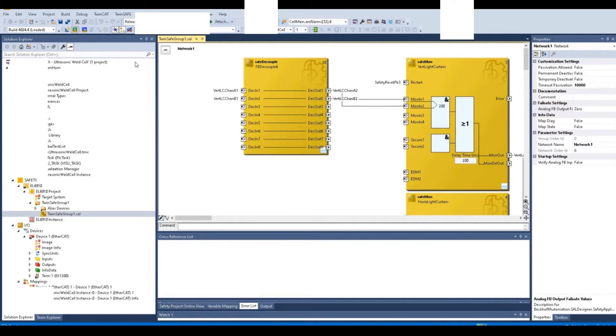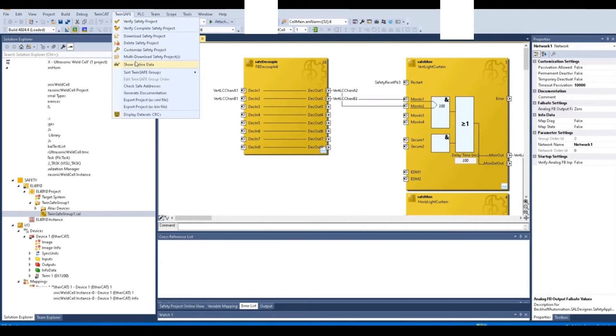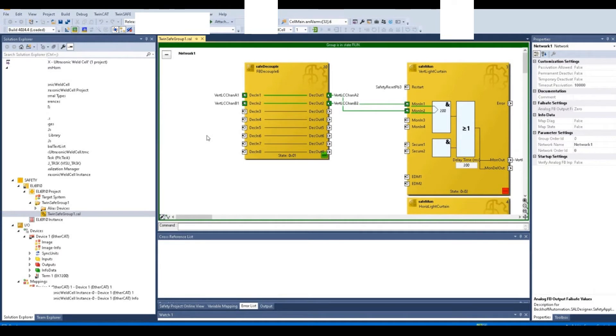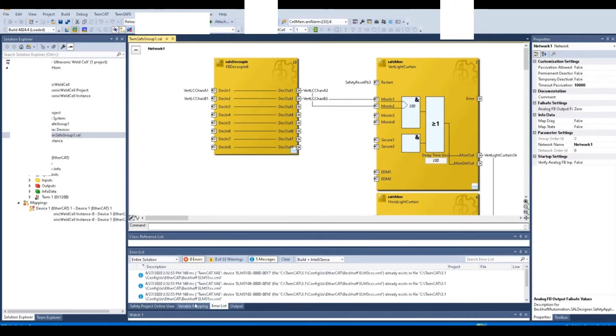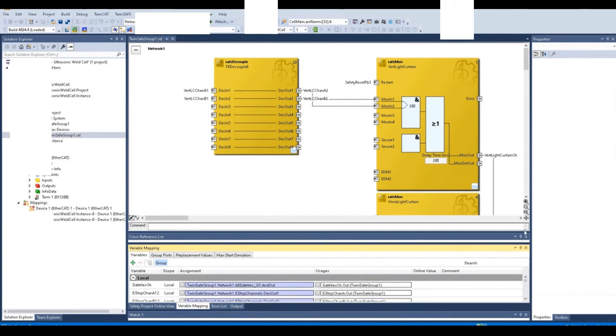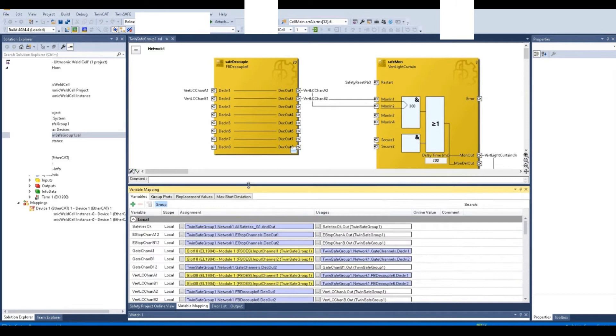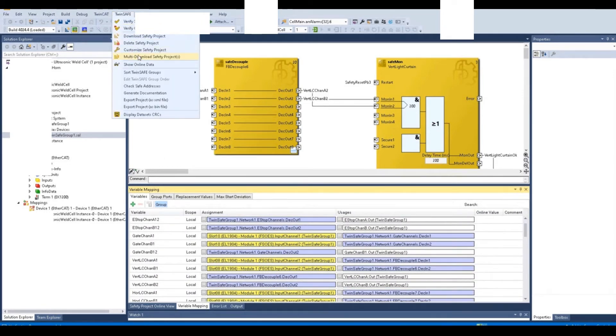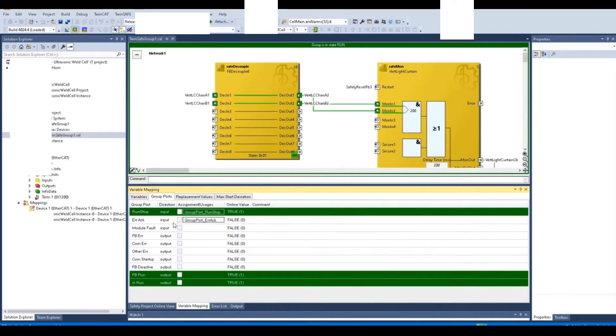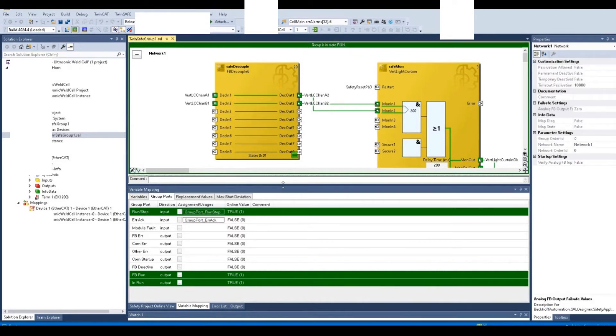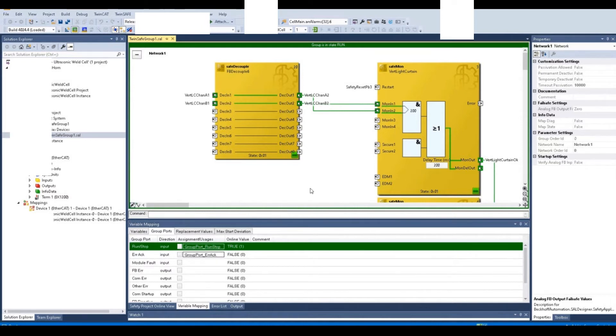Once we turn on the run-stop signal, let's go online again. We will see the online status — if the signal is turned on, it will show green. Let's go to the variable map underneath. In the group ports, there are two important signals: one is the run-stop signal, which must be on to run the safety controller, and error acknowledge, which is used to acknowledge all the errors in the safety logic — usually connected to a physical button on the MCP main control panel.